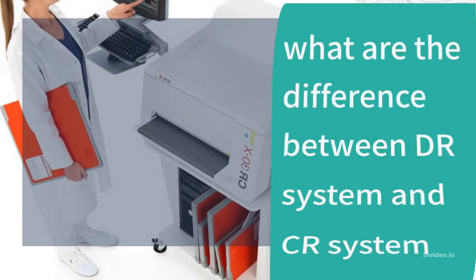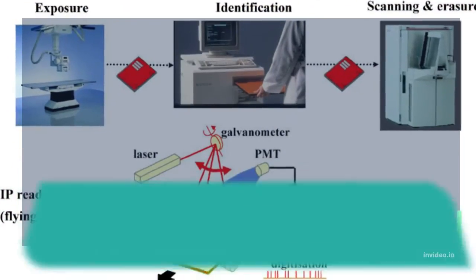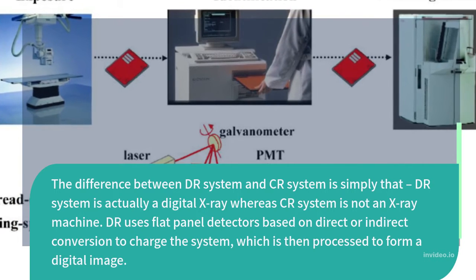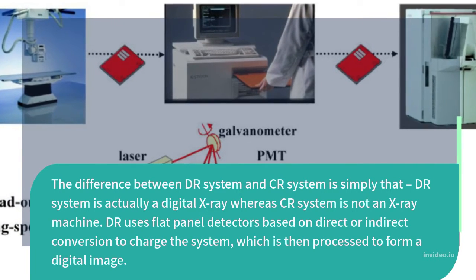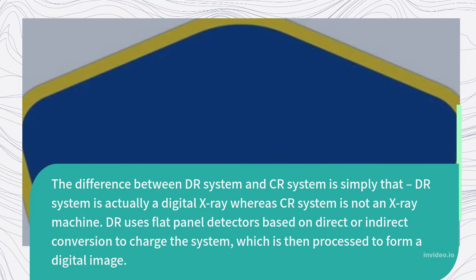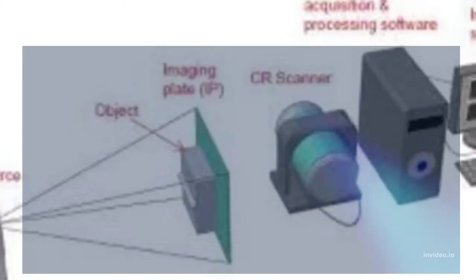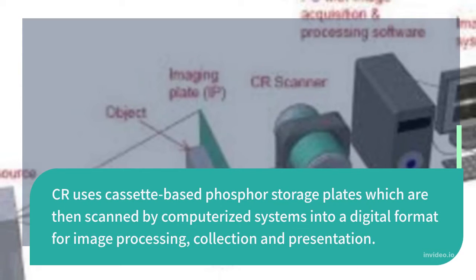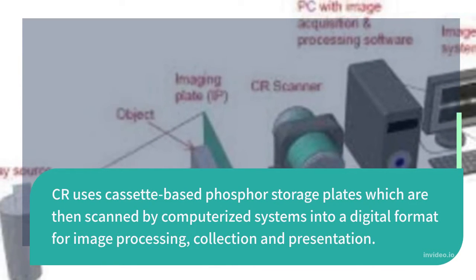What is the difference between DR and CR systems? The difference is simply that a DR system is actually a digital X-ray, whereas a CR system is not an X-ray machine. DR uses flat panel detectors based on direct or indirect conversion to charge the system, which is then processed to form a digital image. CR uses cassette-based phosphor storage plates, which are then scanned by computerized systems into a digital format for image processing, collection, and presentation.